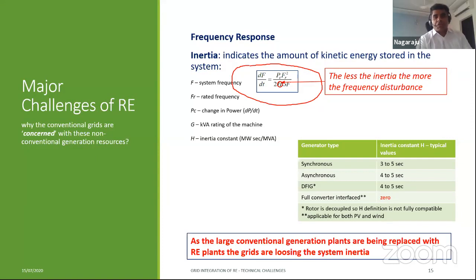So as the large conventional generation plants are being replaced with renewable energy plants, the grids are losing the system inertia. Just to give you an example, August last year, there was a huge outage in the UK around London. Nearly 3 million people lost power. And the reason was the system inertia. It was a sunny day, mostly renewable energy was there, and only 4 conventional plants were running. There was a fault on a transmission line that led to tripping of a nearby conventional plant. Actually, first renewable generation started falling off because of the rate of change of frequency, followed by the conventional generation. So frequency was falling abruptly.